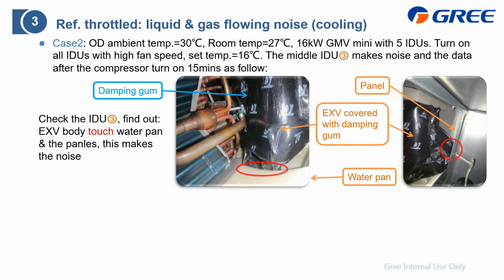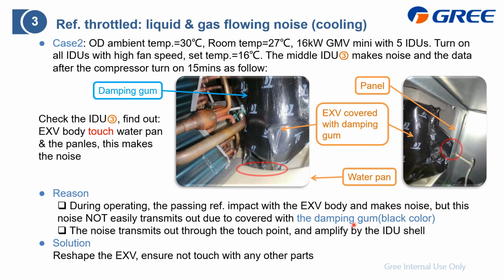We inspected this indoor unit and this is the picture we took from indoor unit 3. We find that this is the EXV body, which is already covered with damping gum, and it touches first the water pan, and then also the panel. We find that with the cover of the damping gum, even if the refrigerant expanding process is a little bit turbulent, it is okay because it has been covered. But if it touches other parts, it will transmit the noise out and also amplify it. So the countermeasure for this is to reshape the EXV to ensure it does not contact any parts, especially these two. And after this, the noise is also cleared.